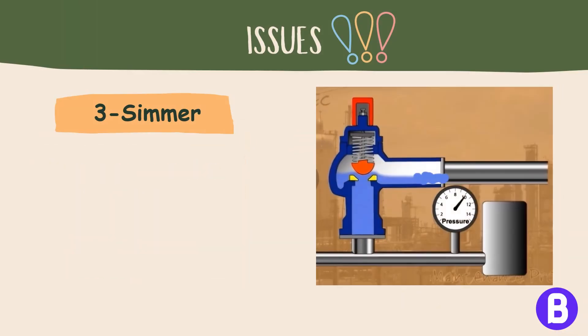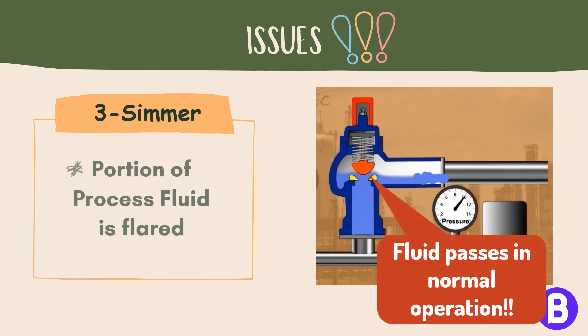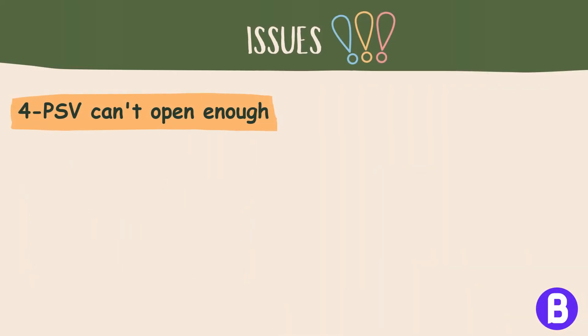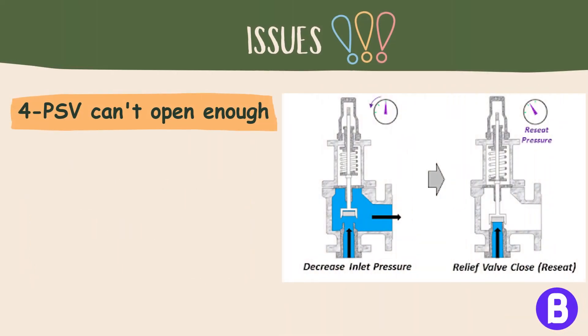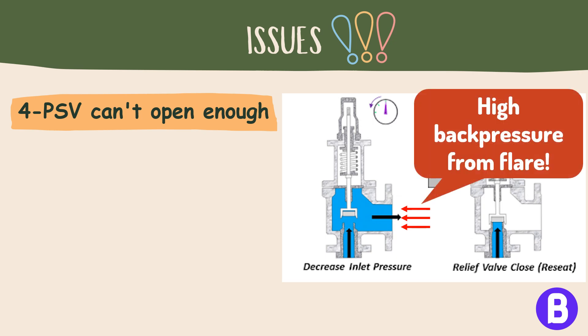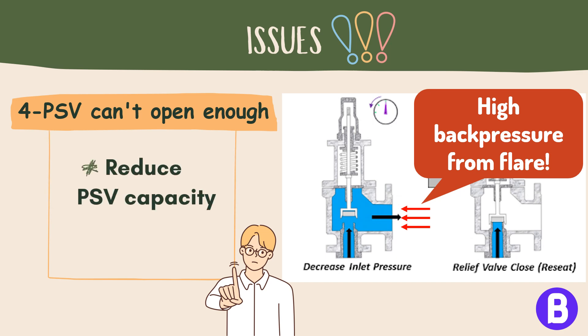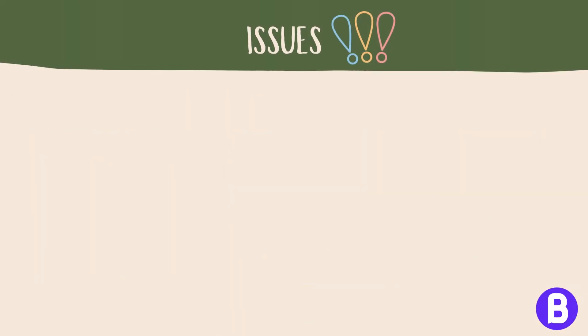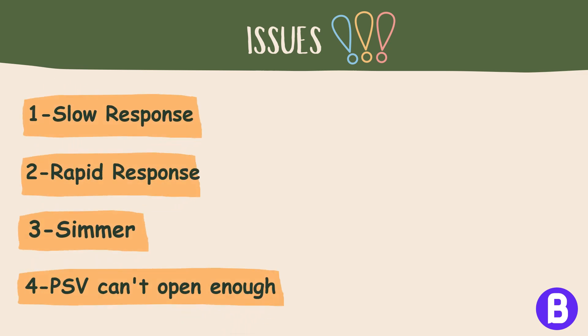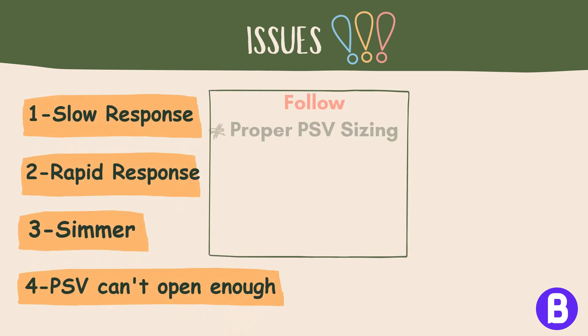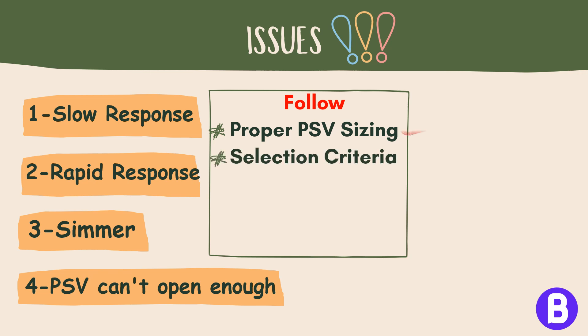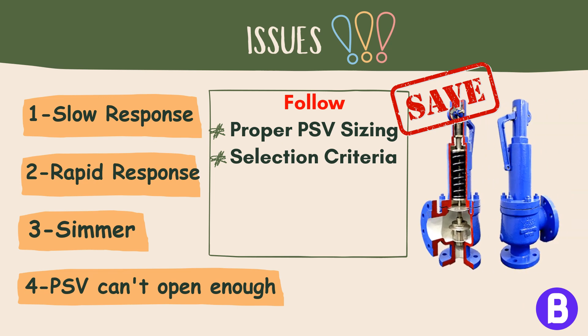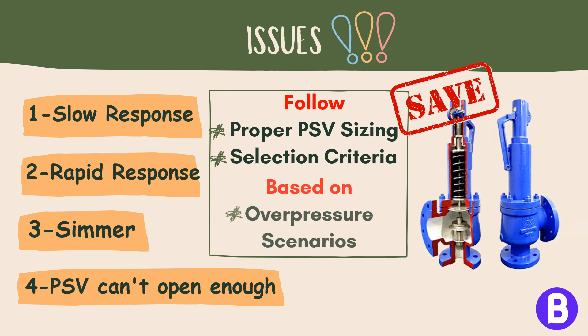Premature opening, or simmer, means that a portion of the process fluid is relieved to flare, which is an undesirable condition. Additionally, a pressure safety valve that cannot open enough due to excessive backpressure — which opposes the lifting force — can alter the valve's response to overpressure and potentially reduce its flow capacity. Each of these issues can compromise the safety and efficiency of a process system, which is why it is essential to follow established sizing and selection criteria such as those outlined in API standards to ensure reliable protection against overpressure scenarios.